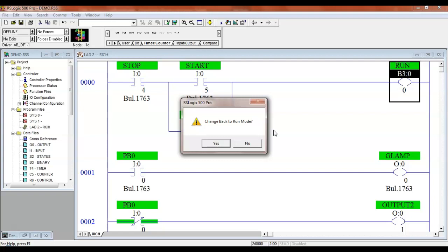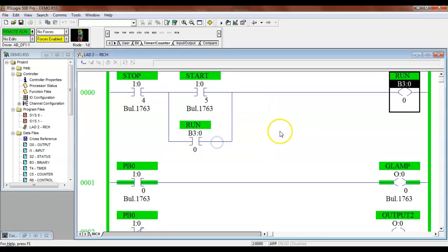They're nothing but contacts. The biggest problem we have with relay outputs is the speed that they can switch. So they can't switch real fast. And plus, they're electromechanical devices, which means they could fail two different ways. So in the old days, it wasn't that important. But now we're dealing with variable speed drives that are controlled with what we call pulse width modulation. And those are very, very high frequency outputs. So if you're going to deal with those guys, then you need to get some type of solid state output.